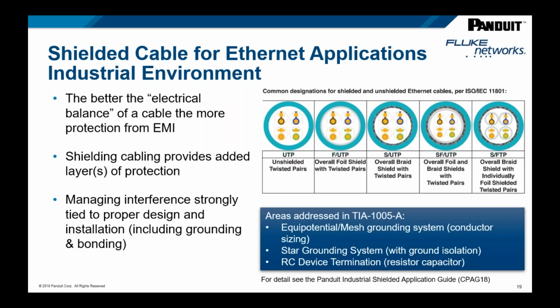Once you get beyond that cable balance, consider the types of additional shielding that you may need. And this is against those noise sources that you would have identified. In the diagram, we're showing you some different versions of shielding that are out there: FUTP, SUTP, SFUTP, SFTP. And there's a slash in each one of those. The S before the slash indicates the shielding around the cable itself, where you're concerned about noise external to the cable. And then the S or the F after refers to the individual pairs. So you may be concerned about noise internal to the cable between pairs, or you might be worried about both of those factors. So cable selection relates to that noise source and also to your grounding and bonding strategy.